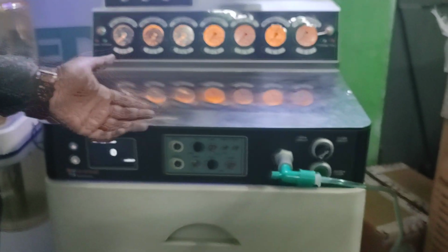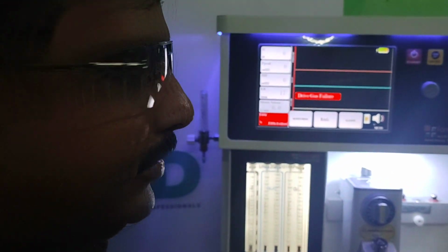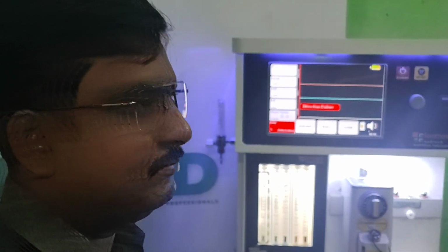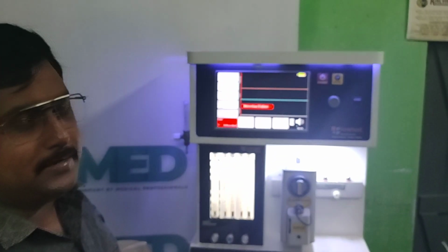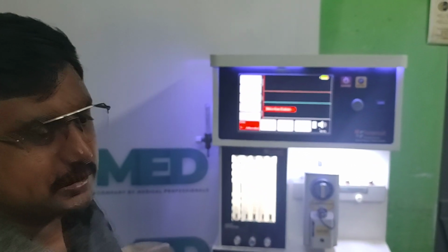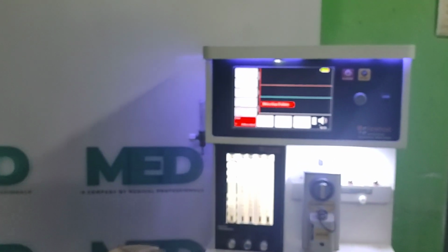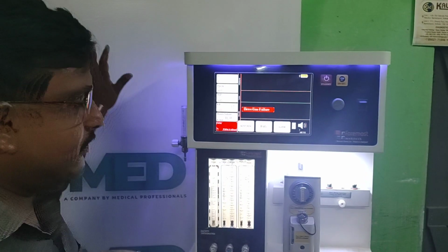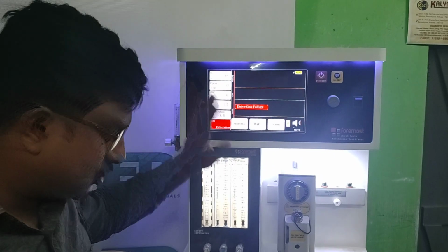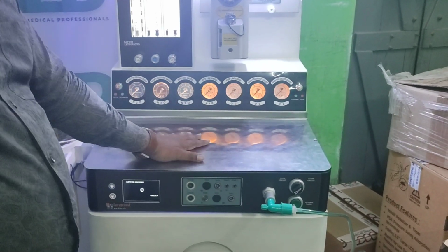The machine is upgradable to ETCO2 and SPO2. Here the panel is there, it can be upgraded to ETCO2, SPO2, or else we can set up monitors with this machine. The monitor will monitor all the patient's vital parameters like NIBP, SPO2, ETCO2, whatever parameters you want. We can put the monitors over here with these machines, or these machines can also be upgraded. You can fit the parameters in the machine, and the output will be connected with this.